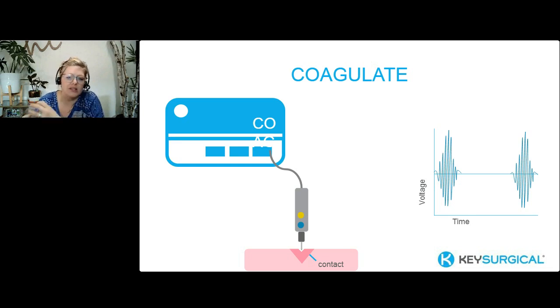And this heats those cells up between that 140 and 190 degree range that we know, kind of desiccation, right, drying, and that protein denaturation occurs. So we're seeing that exact cell response. That off time, on 6% and off for 94%, allows that tissue to cool, and that's where we get that coag effect. And as you can see with this, it does have that thermal spread, that darker pink circle. So right where you're applying the active electrode, but also the tissue surrounding will have a tissue effect.